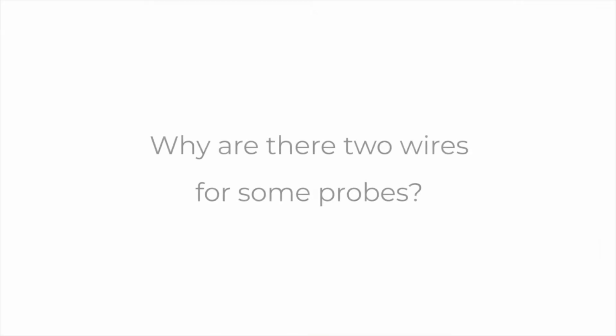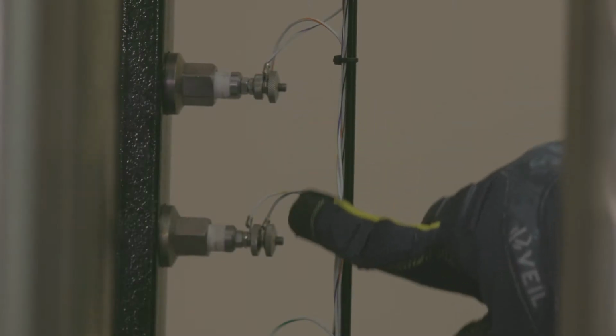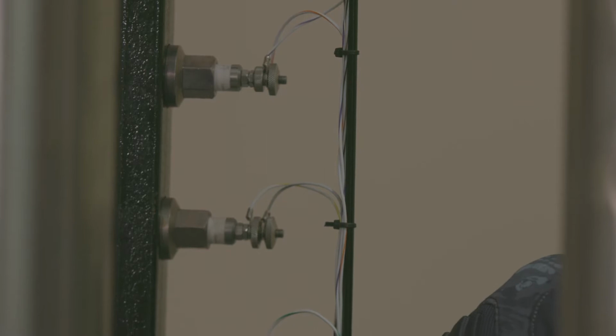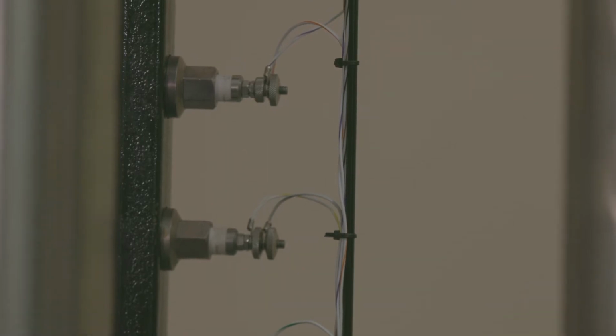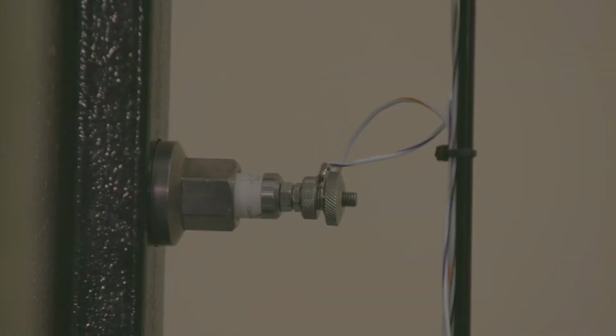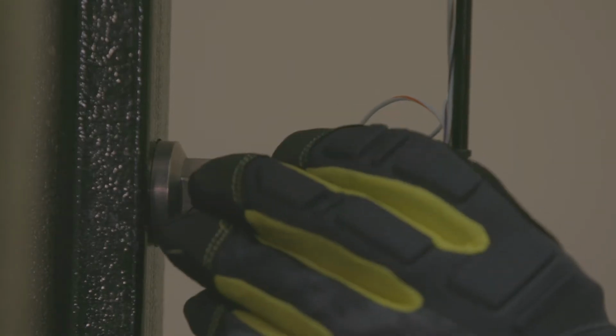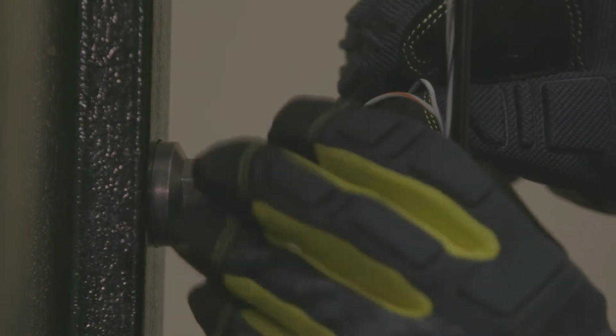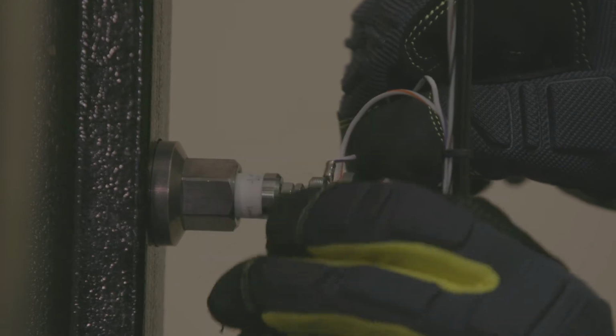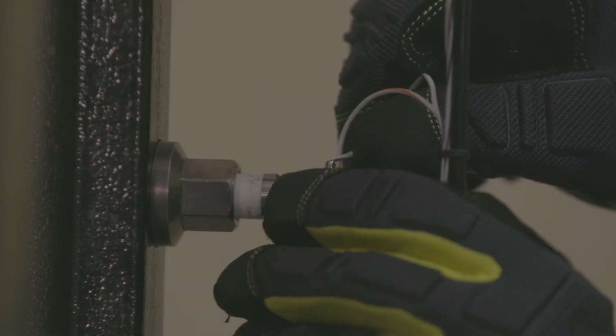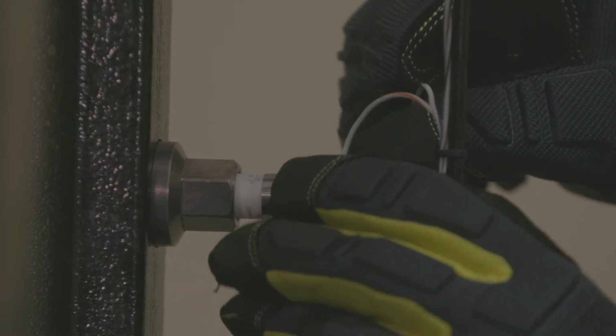Why are there two wires for some probes? The normally dry channels have a secondary continuity circuit between the two wires, which meet at the probe. This is to induce an out-of-sequence system fault. To illustrate, first loosen a wire on a wet probe and it will show dry instead of wet. The fault system will engage.